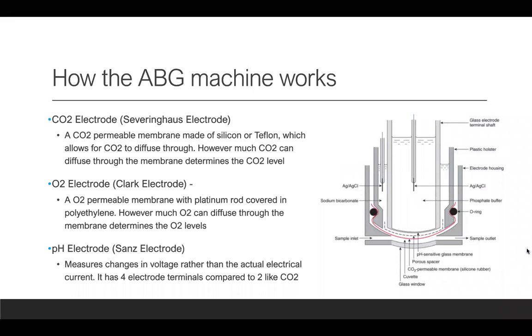So how the ABG machine works, there's three electrodes. The first one I'll talk about is a CO2 electrode, which is also called the Severinghaus electrode. A CO2 permeable membrane made of silicon or Teflon allows for CO2 to diffuse through. However much CO2 can diffuse through the membrane determines the CO2 levels. So essentially the CO2 and the O2 electrodes work the same, and it just detects how much of the CO2 or the O2 is actually getting through the membrane.